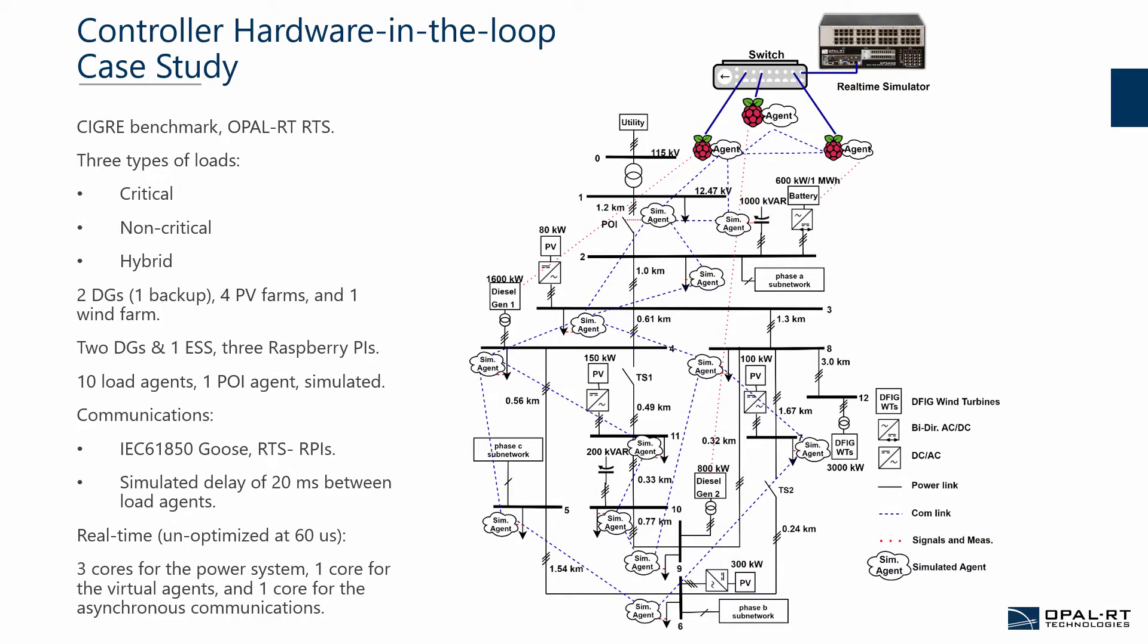A controller hardware in the loop setup was developed and validated to test a microgrid control system. The electrical power network is a CIGRE medium voltage North American distribution benchmark network. It was modified by adding a clear point of interconnection and thereby isolating it from the rest of the electrical microgrid, and by adding various DERs throughout the network. So three types of loads were recognized: critical, non-critical, and hybrid. Also two diesel generators and the energy storage system were controlled by three Raspberry Pis. Whereas the component itself is simulated with the microgrid on the realtime simulator, the controller algorithm was running on the Raspberry Pi. On the other hand, to complete the rest of the distributed control system, ten load agents and one POI agent were simulated with the network as virtual agents.